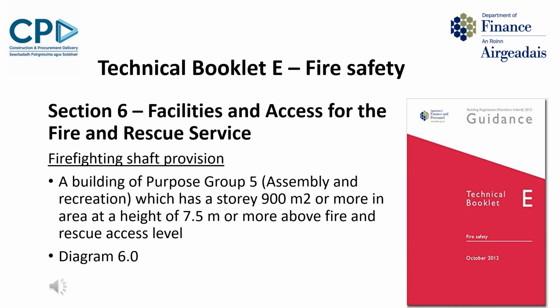Taking these one item at a time, TBE now requires all Purpose Group 5 assembly and recreation buildings that have a story 900 metres squared or more in area at a height of 7.5 metres or more above fire and rescue service access level to have firefighting shaft provision. So all buildings with a story more than 18 metres above fire and rescue service access level require firefighting shaft provision. Already Purpose Group 4 shops and commercial, Purpose Group 6, industrial, and Purpose Group 7A, storage buildings, require firefighting shaft provision at 7.5 metres above fire and rescue service access level. This amendment adds Purpose Group 5, assembly and recreation buildings, to that requirement.